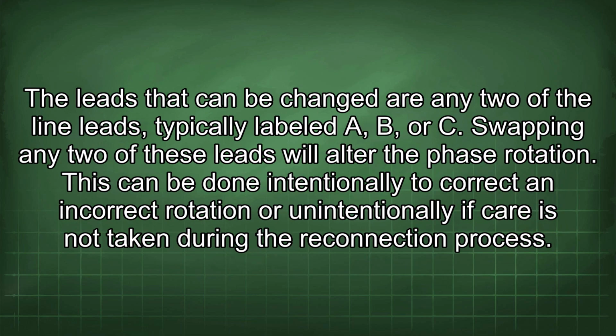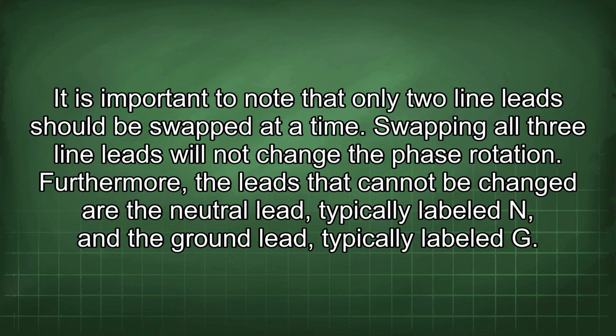The leads that can be changed are any two of the line leads typically labeled A, B, or C. Swapping any two of these leads will alter the phase rotation. This can be done intentionally to correct an incorrect rotation or unintentionally if care is not taken during the reconnection process. It is important to note that only two line leads should be swapped at a time. Swapping all three line leads will not change the phase rotation.